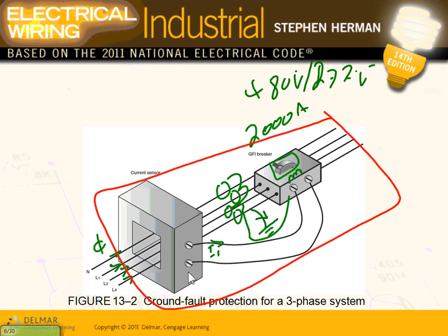That's a load, right? That's why when you have a low ground fault on a 4,000 amp switchgear, say a 1,000 amp ground fault, it's still load. 3,000 amp is still load. All the way to a 4,000 amp ground fault, that's still seen as load.